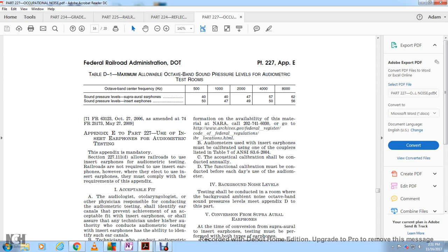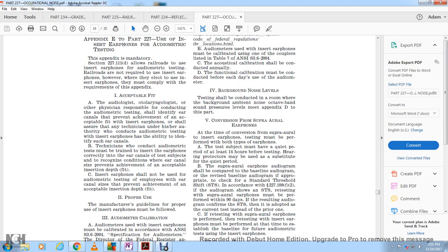Requirement 1: Acceptable fit. The audiologist, otolaryngologist, or physician responsible for conducting audiometric testing shall identify ear canals for which achievement of an acceptable fit with insert earphones can be assured. A trained technician under appropriate authority may conduct the audiometric testing using insert earphones. Technicians must be trained to insert earphones correctly into the ear canal. If the condition or size of the ear canal prevents achieving acceptable insert depth, insert earphones should not be used.